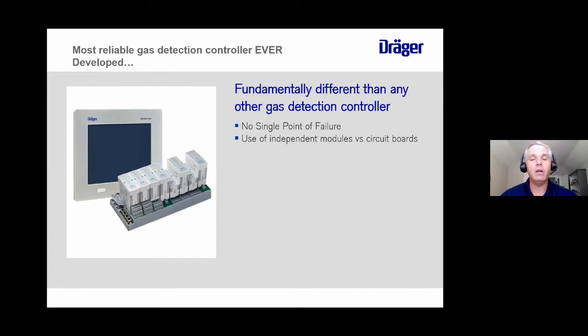And how do we get to that? Well, basically we use independent modules versus circuit boards. And each of these modules is smart, it has its own onboard CPU. We'll go into a little bit of detail on the types of modules in the next couple of slides, but we've got 4 to 20 input modules. We've got relay output modules. We've got bridge modules that allow you to connect legacy Regard systems to this new Regard 7000. So we have all these different modules. And in the design of the system, if you lose one of those modules, you basically just lose the inputs or the outputs from that module, but you haven't lost the whole safety system.